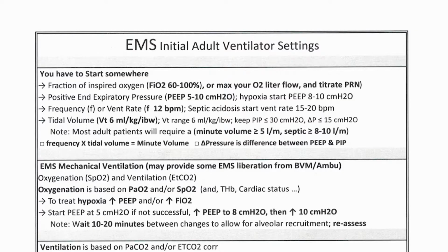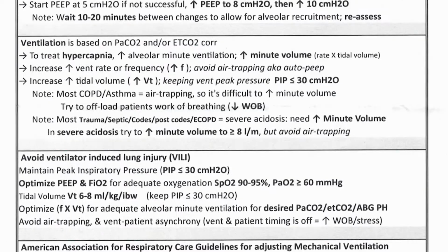So PEEP and FiO2 for oxygenation, rate and tidal volume for ventilation. You're going to be limited with these vents. The vent I've seen that you're going to use, again, it capped out. Every time we tried to combine a rate and a volume to get beyond a minute volume of 8, it wouldn't let us do it. It would actually drop the targeted tidal volume. So it already had its own built-in formula. So if I jump the rate up to 20 on a given height that I had at a rate of 12, it's going to drop the tidal volume down to where that rate and that tidal volume gets a minute volume of 8.0. So it's automatic.